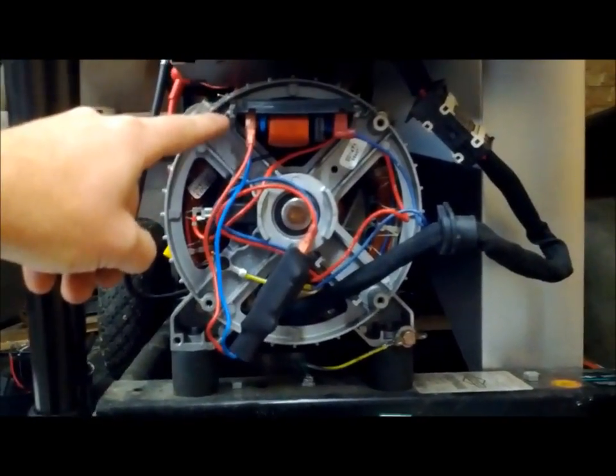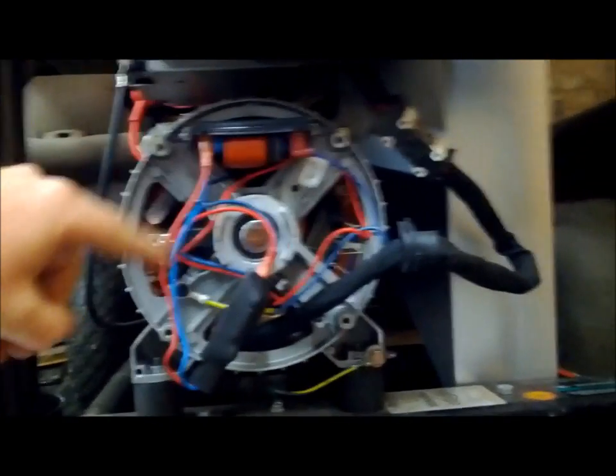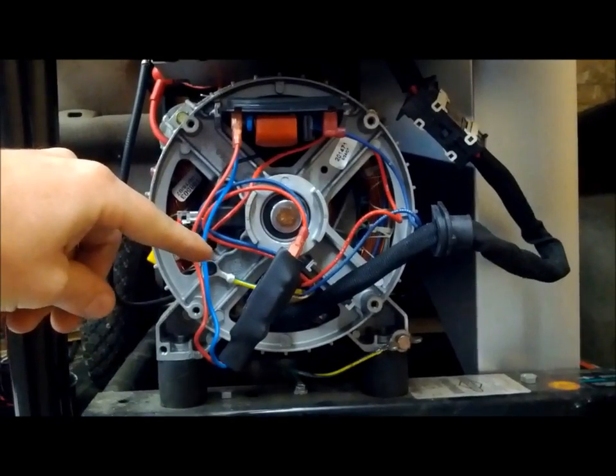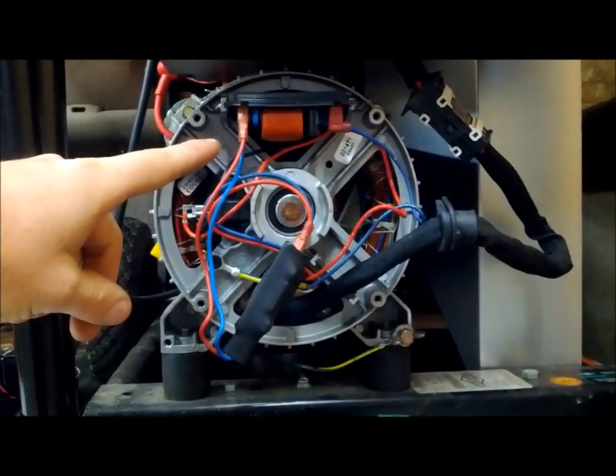Since we know it's our automatic voltage regulator up top here, we're going to change that. We've got a brand new one, and with the new one, you do not need the inline booster. So we're going to remove that, hook the wires directly up to our automatic voltage regulator.